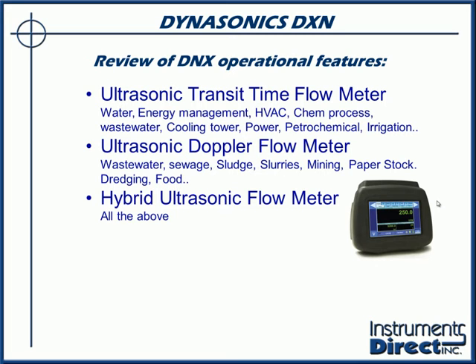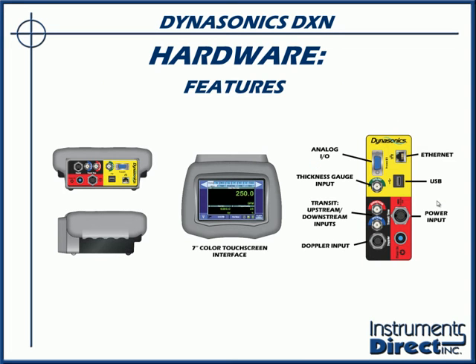Should you have an application that also has heavy levels of suspended solids, such as wastewater, sewage, sludge, slurries, mining, paper stock, dredging, and so on, or an application that goes back and forth, the ultrasonic Doppler can take care of your heavy solid application. And the hybrid is the back and forth function, where you can have both the transit time and the Doppler sensors on the application, or you have the ability to just put the transit time sensors on and do a transit time application, or just put the Doppler sensors on and do a Doppler application. So this device has everything in the same box to do your whole gamut of liquid applications.